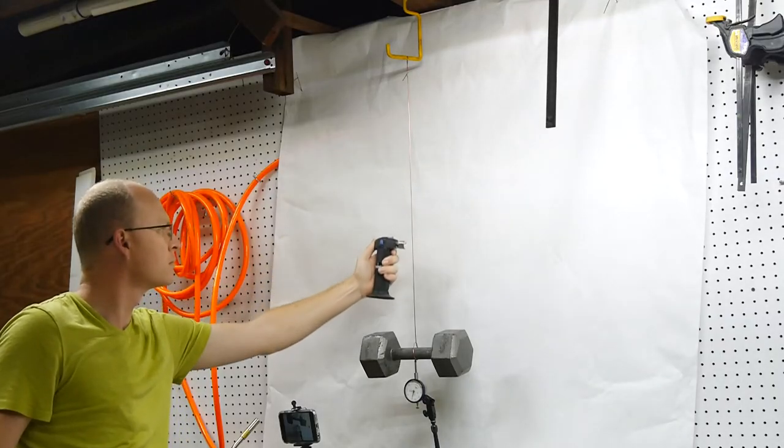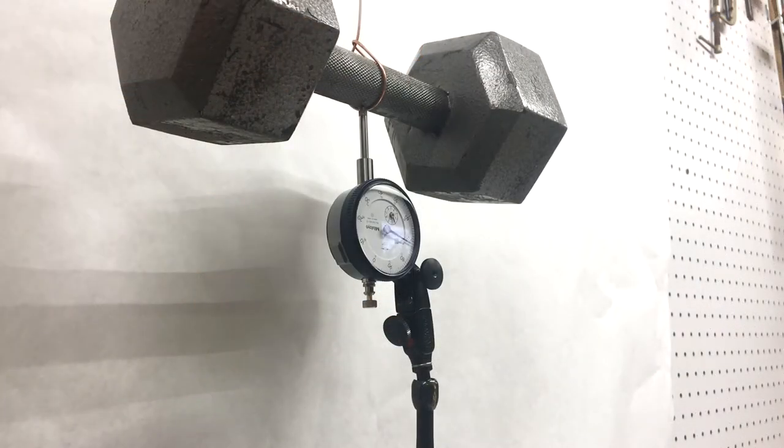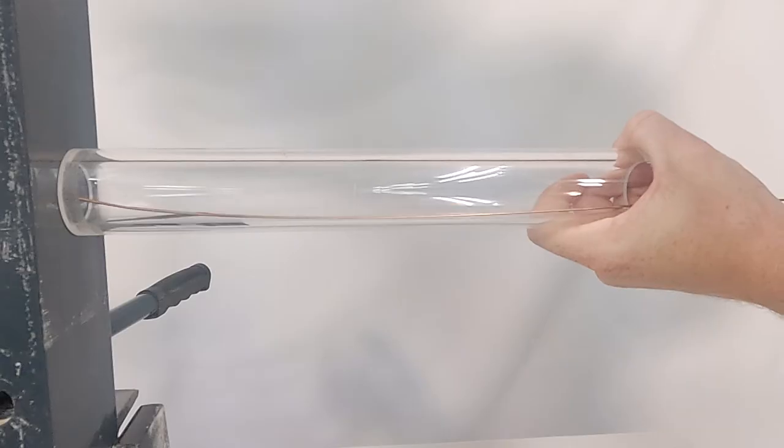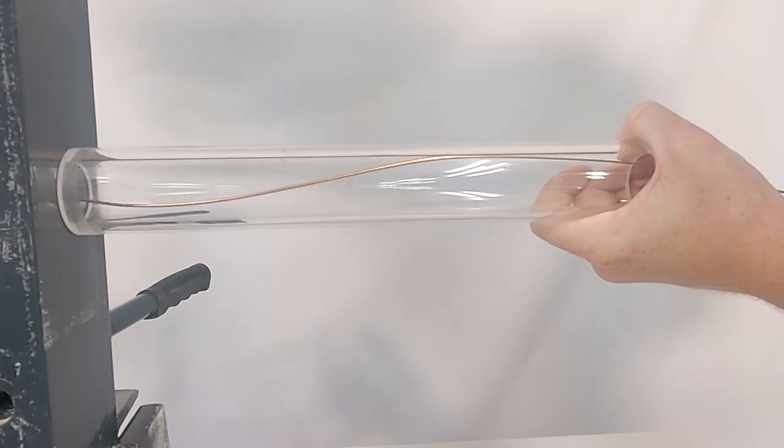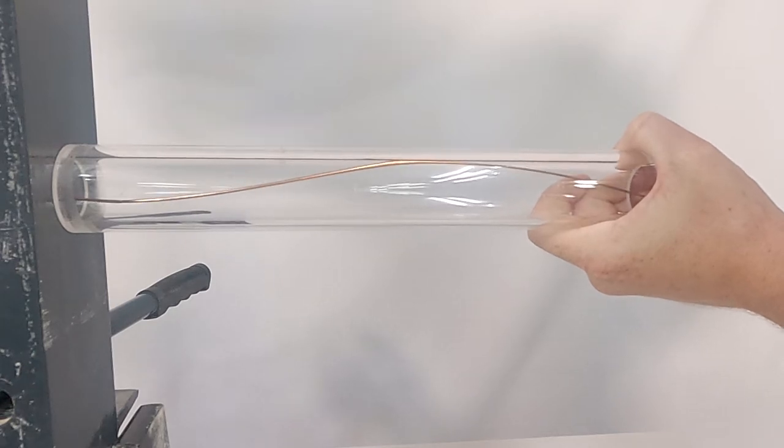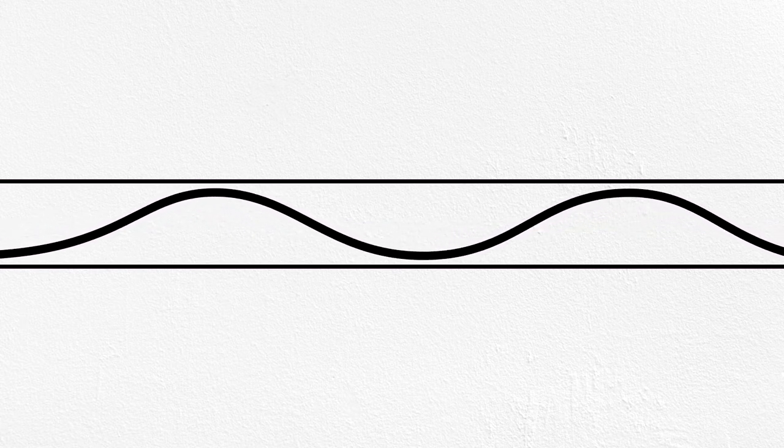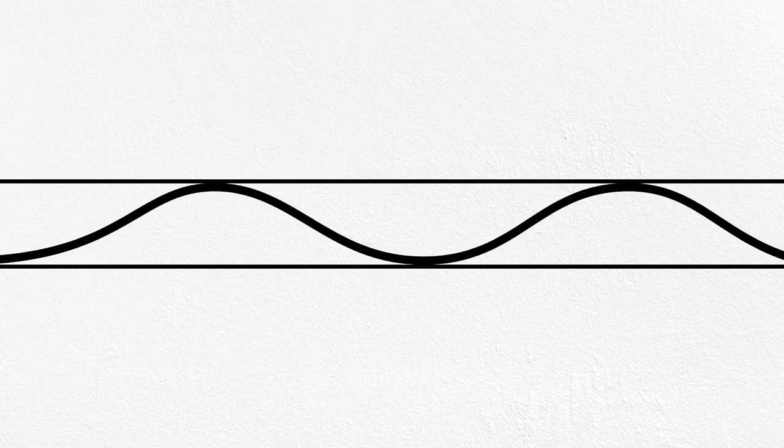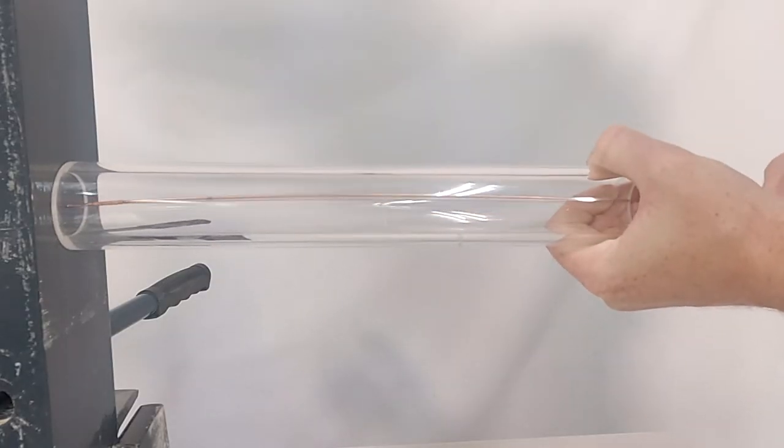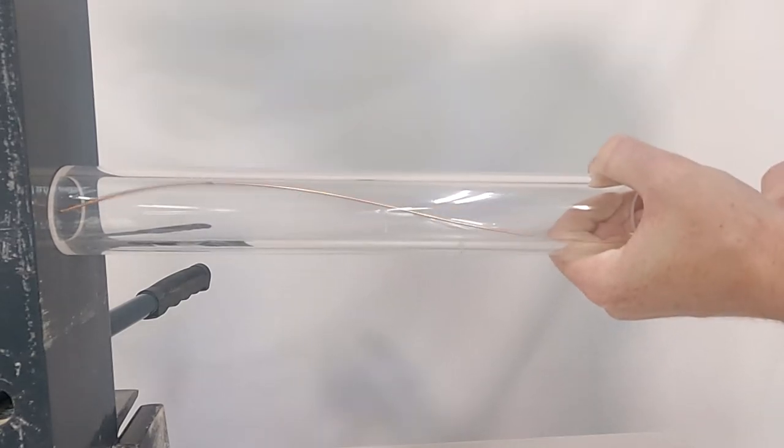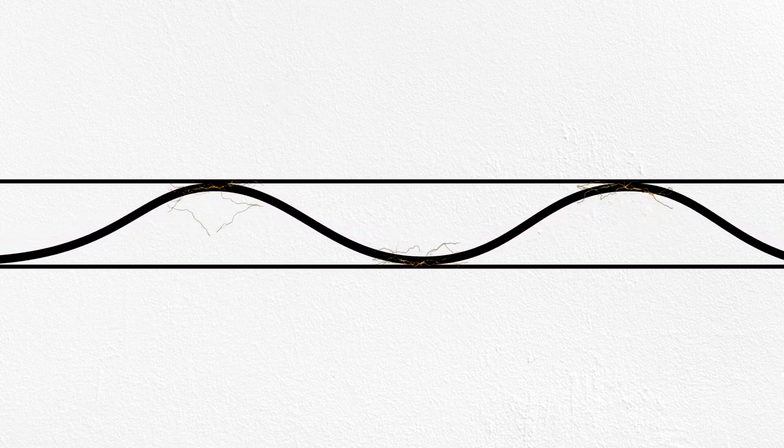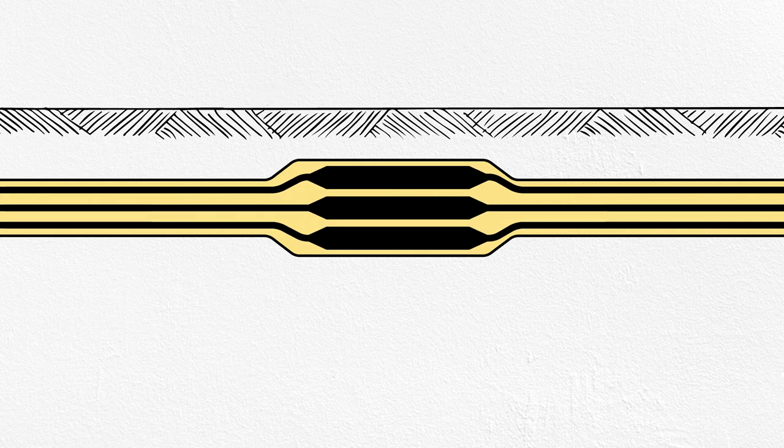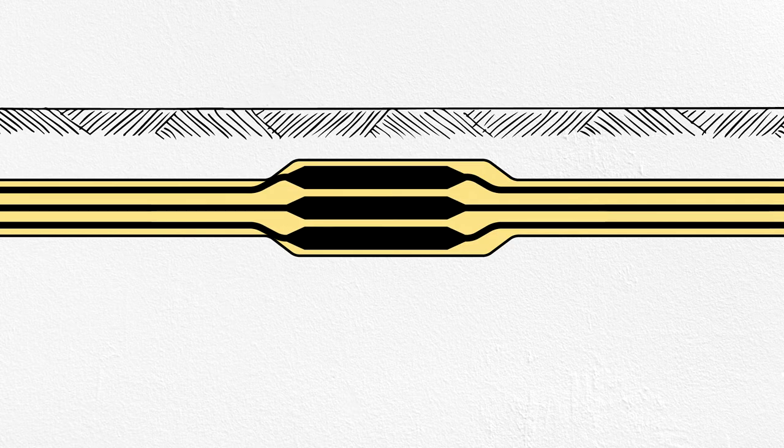As you might know, many materials expand or contract with changes in temperature, and that's true for the copper conductors used in underground transmission lines. When these lines expand within the outer pipe, they often move and flex in a process called Thermal Mechanical Bending, or TMB. If not carefully designed, these bends can become tighter than the minimum bending radius of the cable, exceeding the allowable stresses within the material. Over hundreds or thousands of cycles of TMB, the paper insulation around each conductor can begin to soften or tear, eventually leading to a dielectric breakdown. In other words, arcs and short circuits. TMB can also pull large diameter splices into narrower sections of the pipe, causing them to rub and abrade. That's what happened in 1989 to the Scattergood Olympic Line.